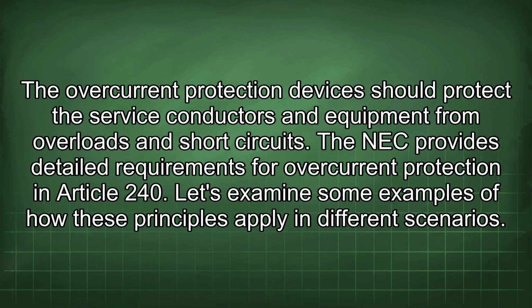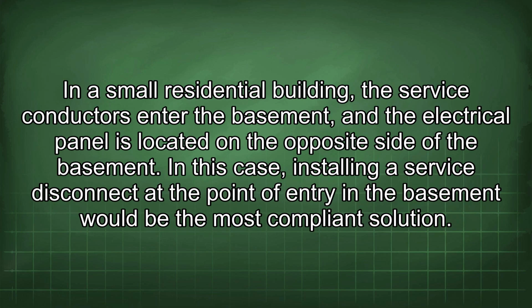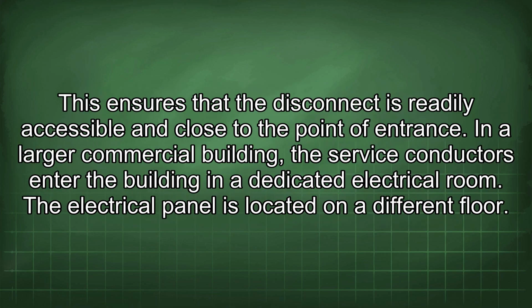Let's examine some examples of how these principles apply in different scenarios. In a small residential building, the service conductors enter the basement, and the electrical panel is located on the opposite side of the basement. In this case, installing a service disconnect at the point of entry in the basement would be the most compliant solution. This ensures that the disconnect is readily accessible and close to the point of entrance.